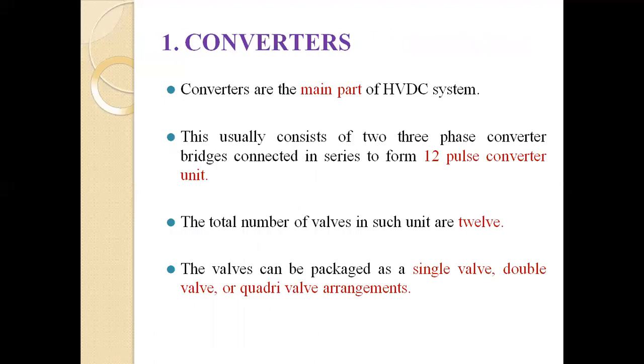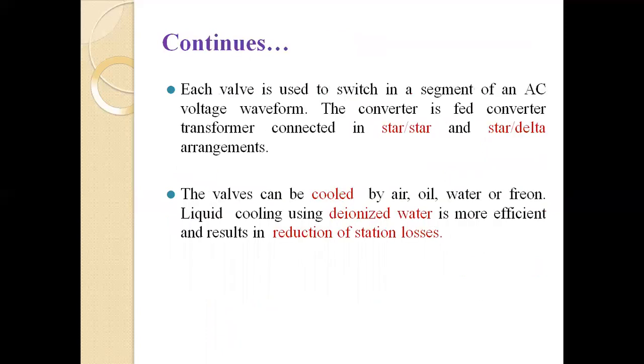So what is the function of the converter? First part is the converter. The converter is the main part of the HVDC system. This usually consists of two three-phase converter bridges connected in series to form a 12 pulse converter unit. The total number of valves in such a unit is 12. The valves can be packed as a single valve, double valve, or quadri valve arrangement.